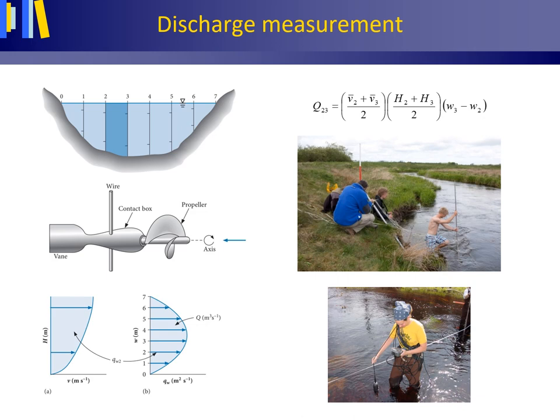At the beginning of the last lecture, the Pitot tube and combined Pitot tube were introduced for measuring the velocity head to determine the water velocity along a streamline. A well-known instrument for determining the water velocity at different locations and depths in a stream is the Ott-type current meter, named after Albert Ott. When the propeller is set as shown, the water flow is from the right. One may simply determine the water velocity using an electronic device that keeps track of the number of revolutions of the current meter's propeller during a set time interval. The flow velocity can then be determined from a calibration equation provided by the manufacturer that links the water velocity to the number of revolutions.